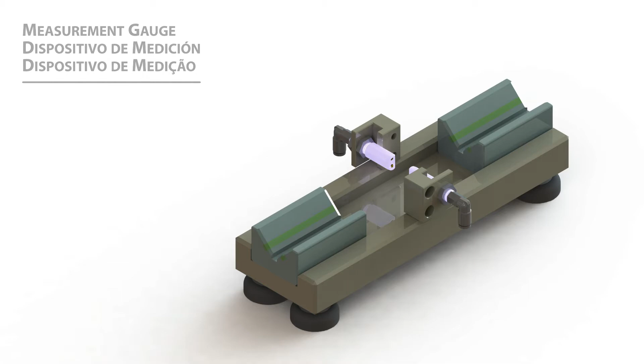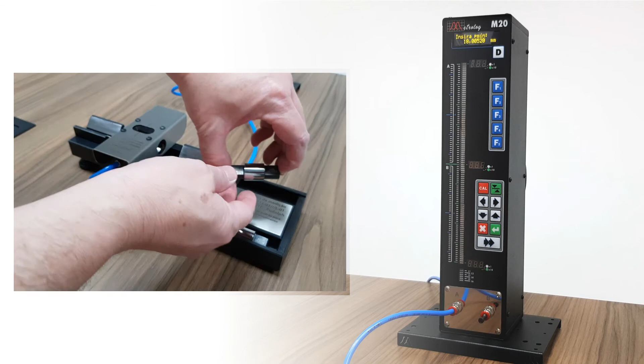Calibration. Associated with a Metrology M20 measurement column, the calibration and referencing process is simple. The cal key is pressed and then the measuring channel is confirmed. The minimum master setting disc is inserted into the device and confirmed.